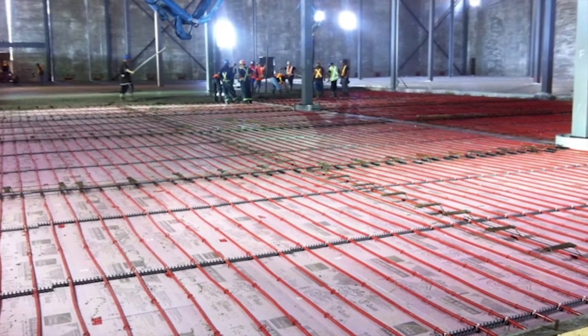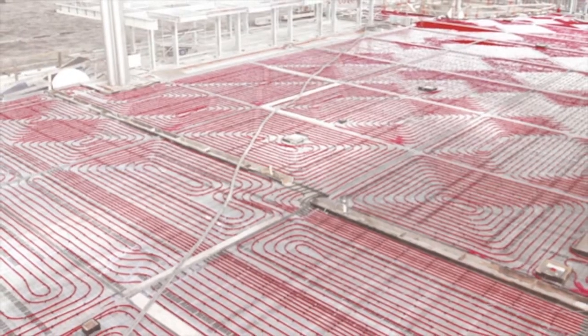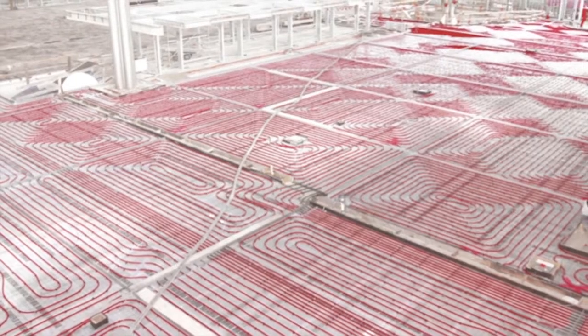Your foundation becomes a large thermal mass that stores heat energy, and water moves more heat than air does. Because radiant heat provides silent, even heating, zoning is not as much of a priority. But we still broke the building up in zones based on different occupancy types by using balancing valves to adjust the flow rate of the water.